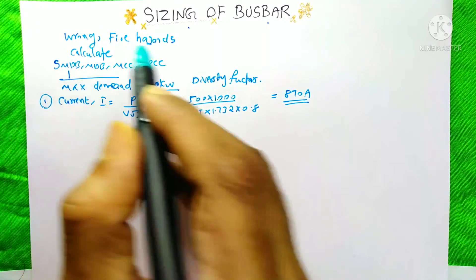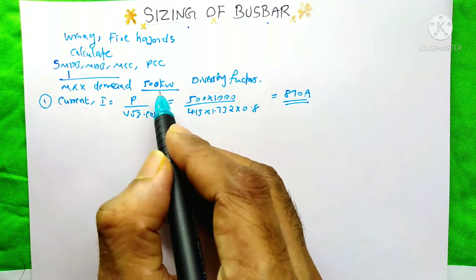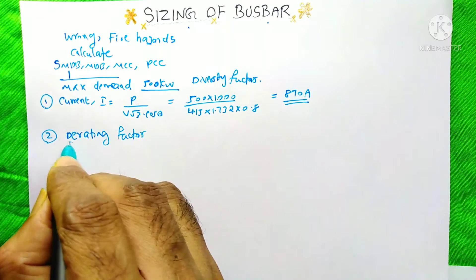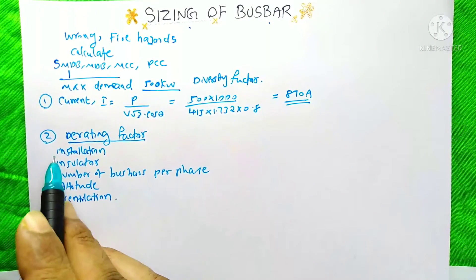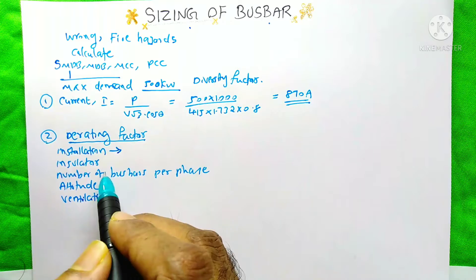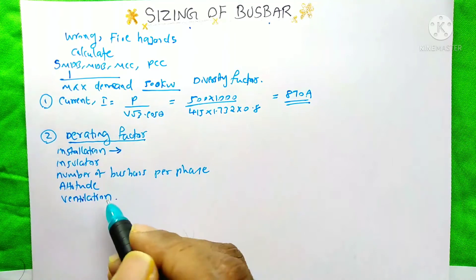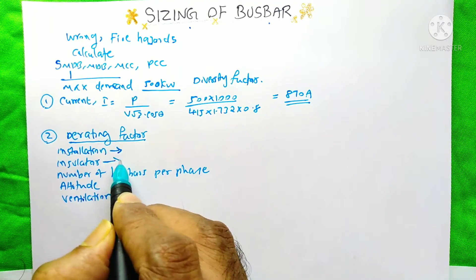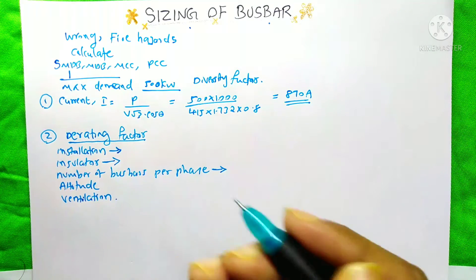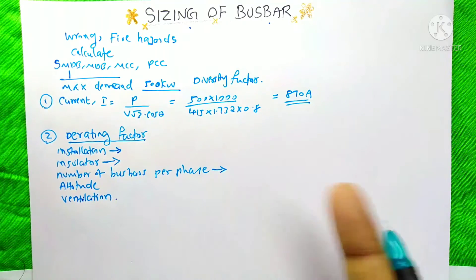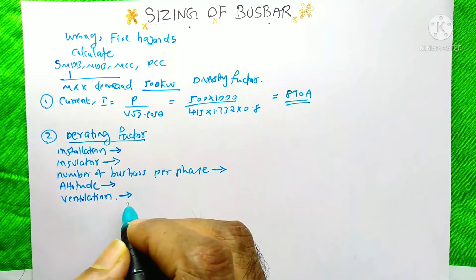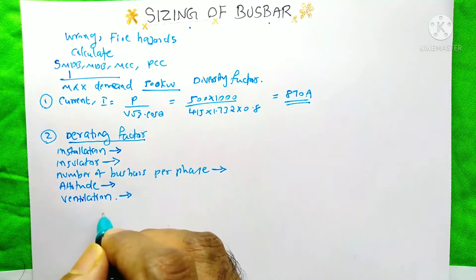This is the first step of sizing the bus bar — finding the current for the maximum demand. The second step is applying the derating factor. Derating factors depend on: installation location, the insulator at the top and bottom of the bus bar, the number of bus bars per phase, the altitude from sea level, and the ventilation.